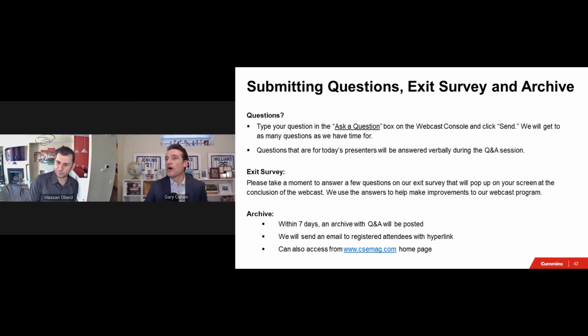Got it. And let's just do one more question here. I think that's about all we have time for. Do we have to provide sync equipment with two generators in parallel, both starting at the same time? Not if you specify the integrated ones. You don't have to have sync equipment. That genset controller will have all the synchronization, that little board that I just showed you a picture of. Like I said, it is the size of your iPad. It has everything in it to do the synchronization and sync checks and the protection and the load sharing between the generators. So you would not need to specify any additional sync equipment. Hopefully that will help you. If we can take that off your mind, then you can focus on other things when you're designing the system.